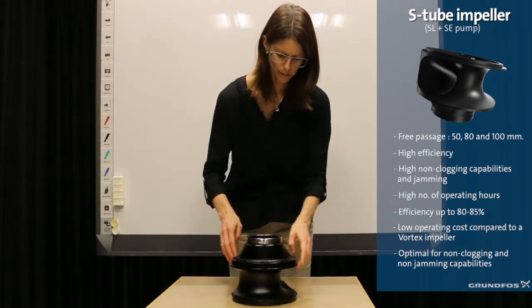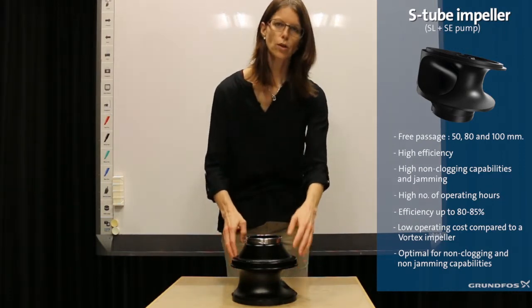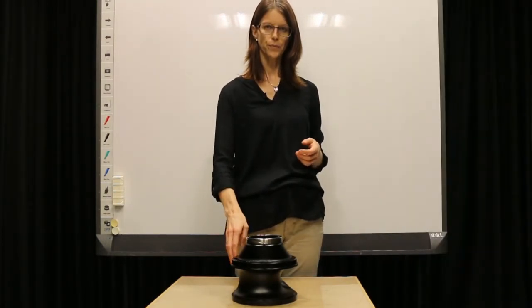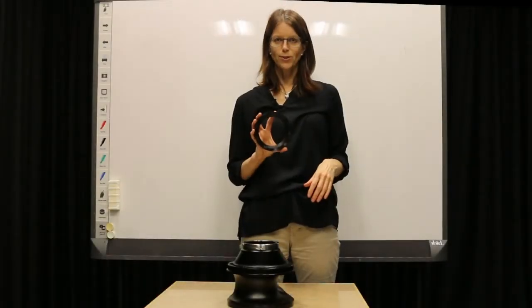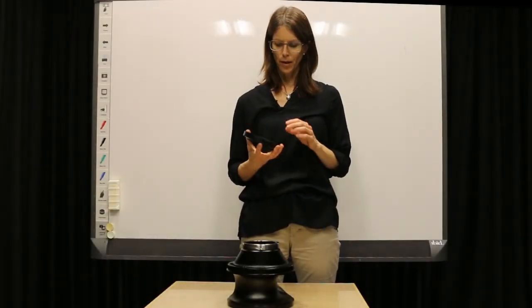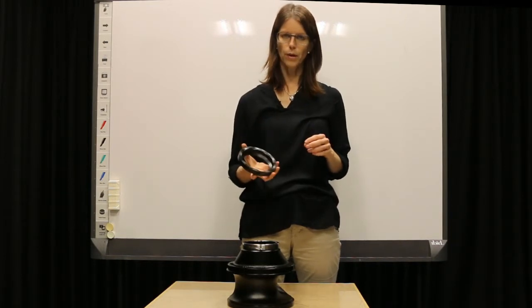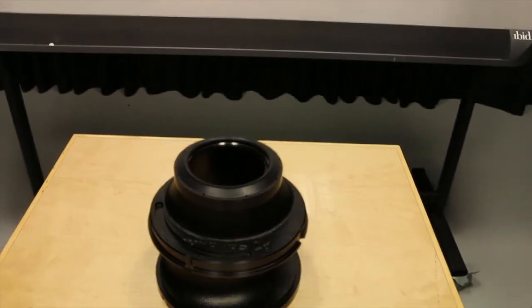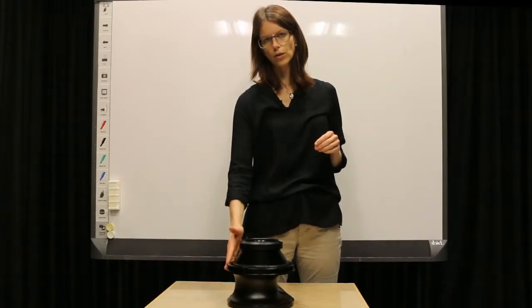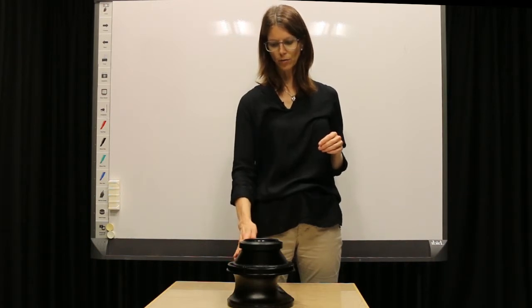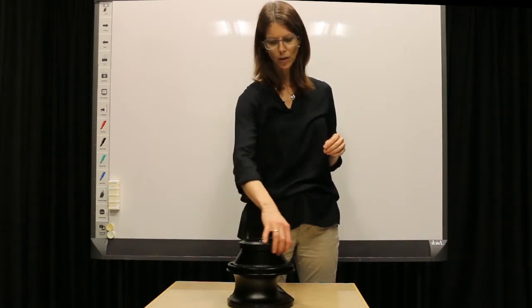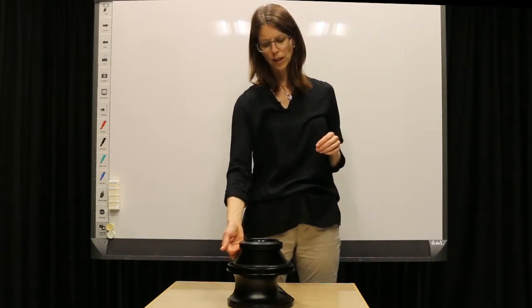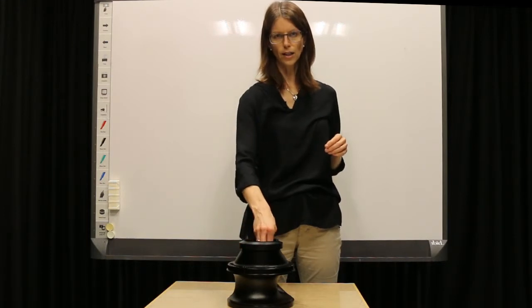On the sides there are cut-outs which also reduce the risk of jamming. Additionally, a wave-shaped ring is mounted in the pump housing running against the spin-out ring. When wastewater tries to run back to the inlet, the wave-shaped ring creates a pulsating effect that drives flow back into the inlet.